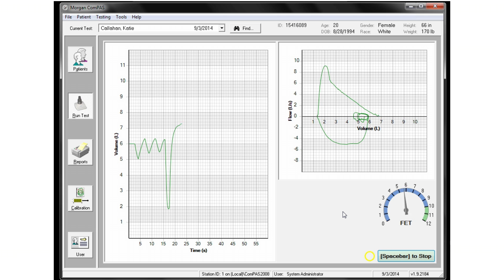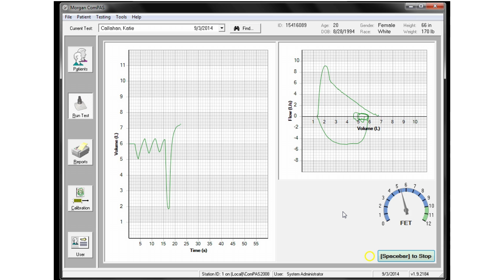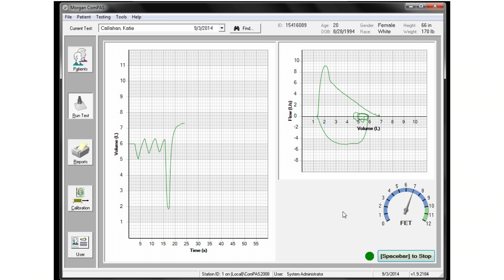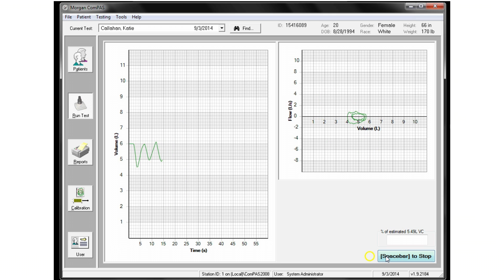The forced effort should continue for a minimum of six seconds and in cases of COPD can be much longer. The end-of-test detector will turn green when the volume change has ceased, at which point the subject can be instructed to breathe in. On subsequent efforts, a percent of best FVC meter is also displayed.